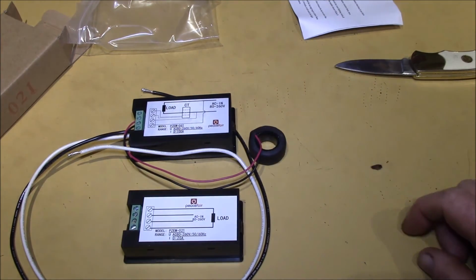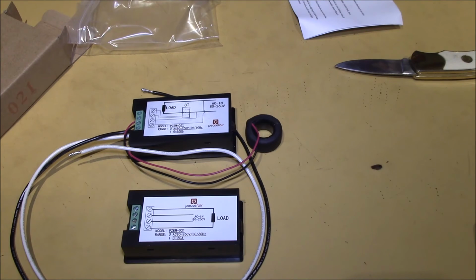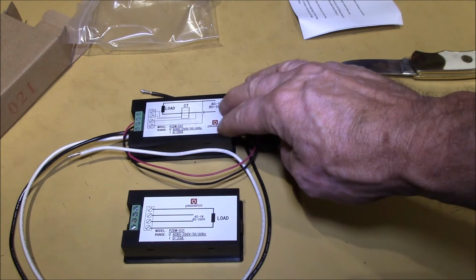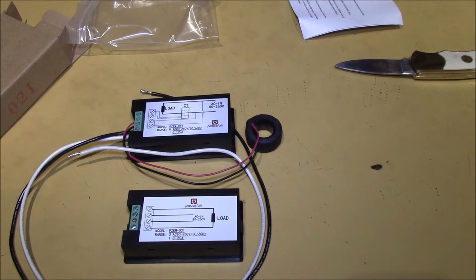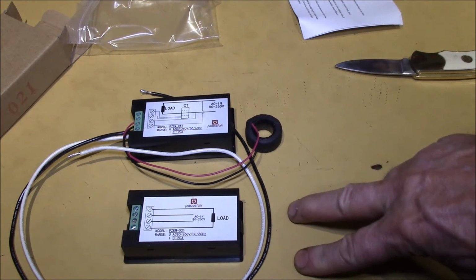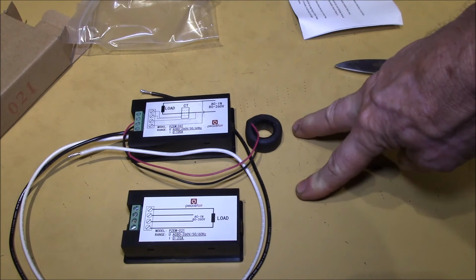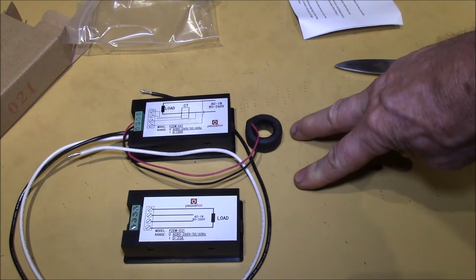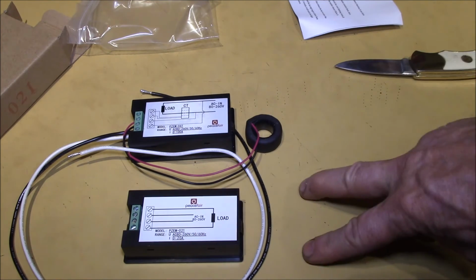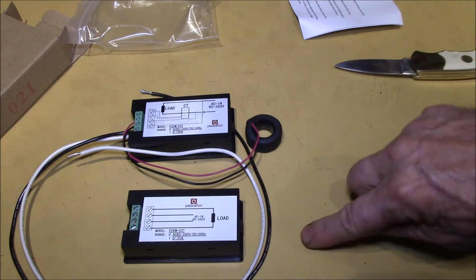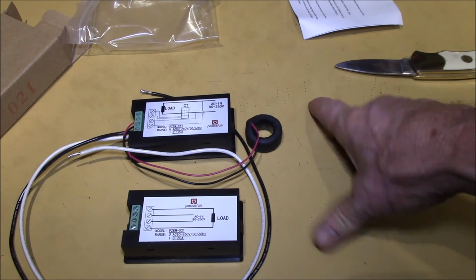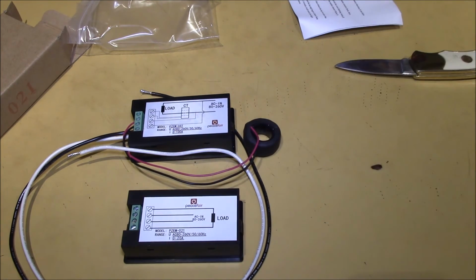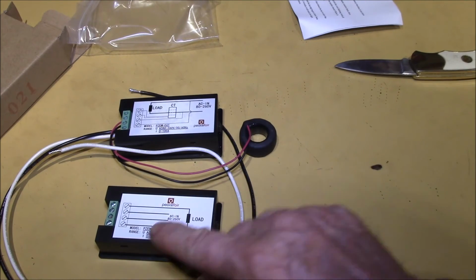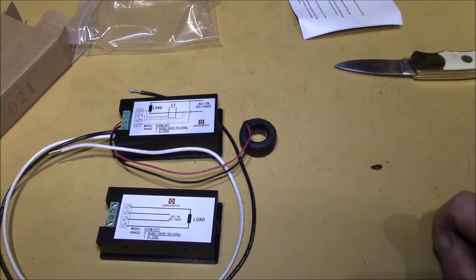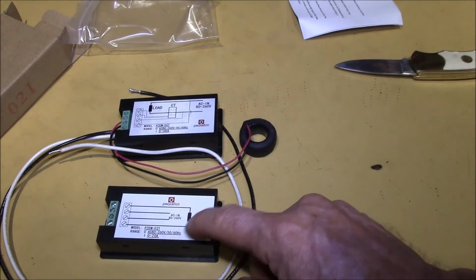This 230 volt, 240 volt split phase kilowatt meter is at a viewer request. Had quite a few viewers ask, how do you set one of these up? At least in the US, where we have the split phase, you have 120 volts, neutral, and then a second leg or a split leg with the 120 volts. So you have 120, 120, and then you have your 240 volts between the two lines. And you pretty much wire it up the same way, so I'll show you how to do that. So this is the PZEM-021 AC panel meter, 20 amps with an internal shunt.